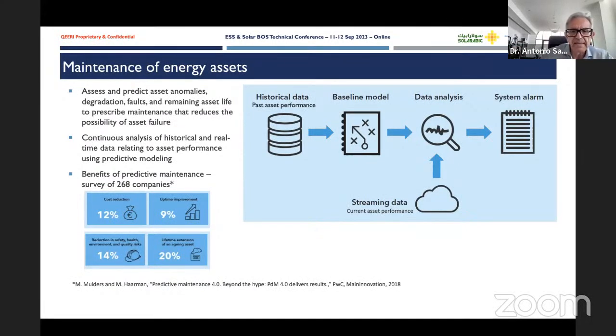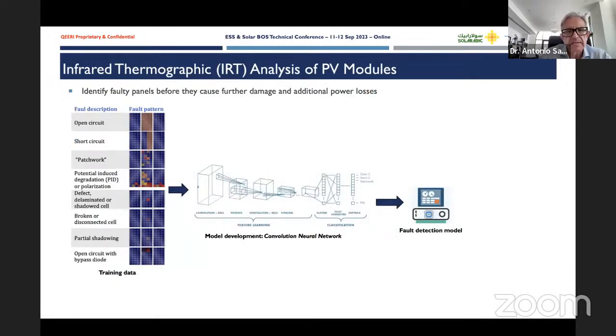I want to give you an example of this, and I think this is my last example, with respect to thermographic analysis of PV modules. So, when you have a PV plant, modules get damaged. It's very important to recognize this damage, these faults, as soon as possible for two reasons. First, to avoid further damage, and then, obviously, to avoid additional power losses.